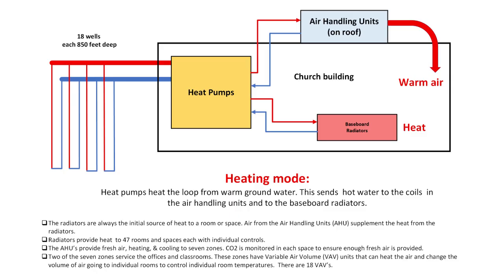The radiators are always the primary and first source of heat for all of our rooms because of the way our building's built. Then the air handling units blow additional warm air as needed to take it up to whatever temperature is required. We have 47 different radiator zones to individually control the temperature in the various rooms. So the building control system will set the rooms to a pre-programmed temperature or adjust them to the thermostat in the room if the person in the room changes the temperature within the band that we allow. You can't go crazy with changing the temperature.